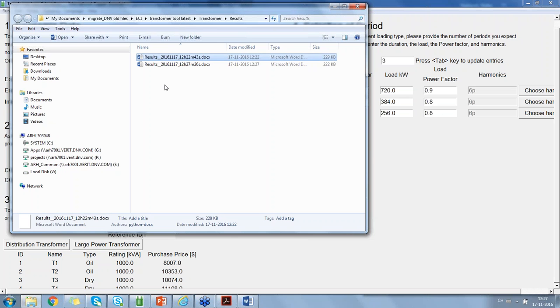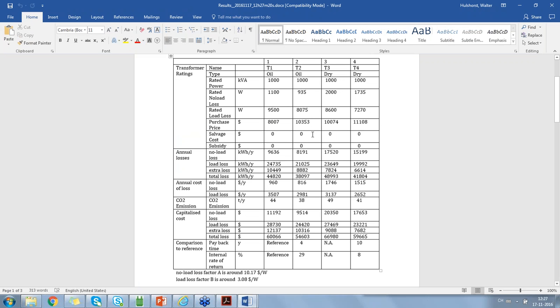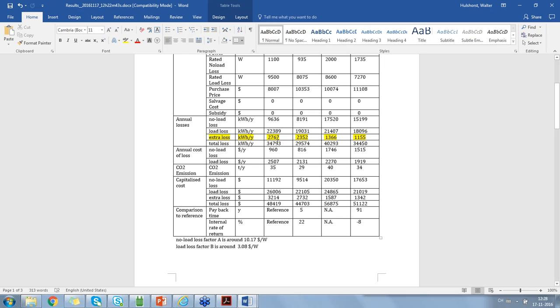The results are now given in this situation, and there I have the same output. It's still a Word document, but now we can have a look at the extra losses we have in total, which are caused by the harmonics. In the situation over here, you will see that transformer 1, let's remember that one, has about 10,000 kilowatt hours per year, a little bit more in total, as extra losses. If we go back to the other one where we didn't have any harmonic loading, it was 2,700. So you can see immediately the impact in case you have a very high harmonic loading. In this case, the extra losses are almost 3 or 4 times higher.